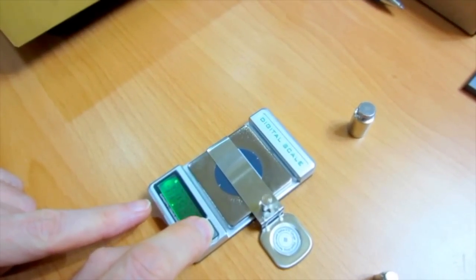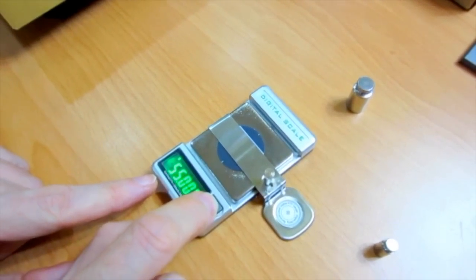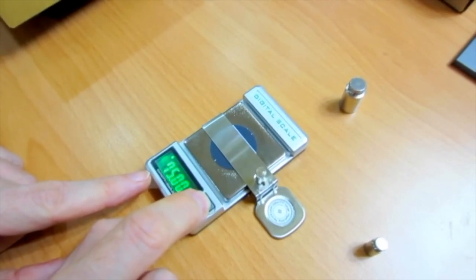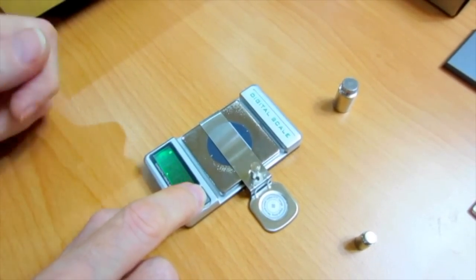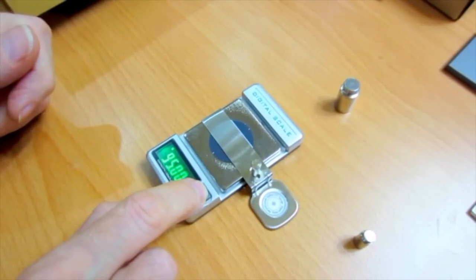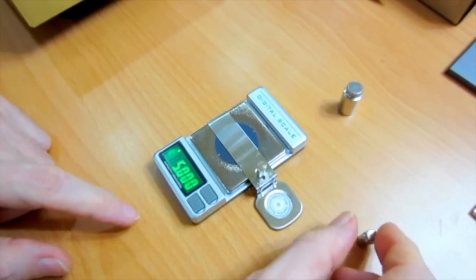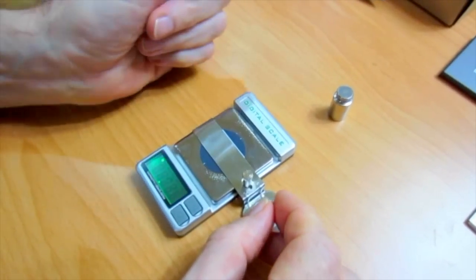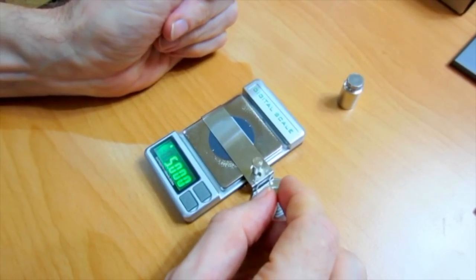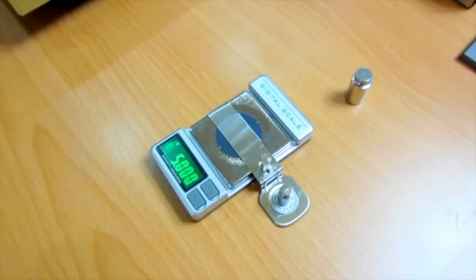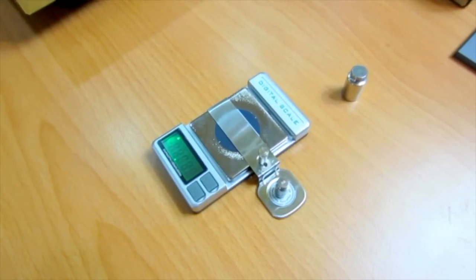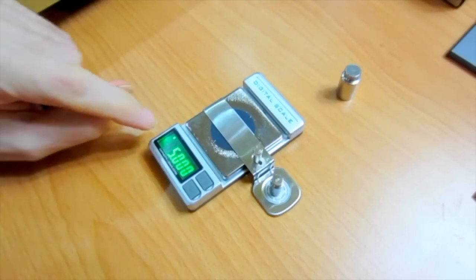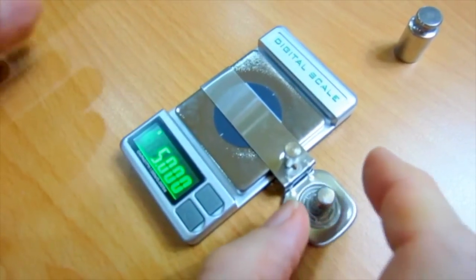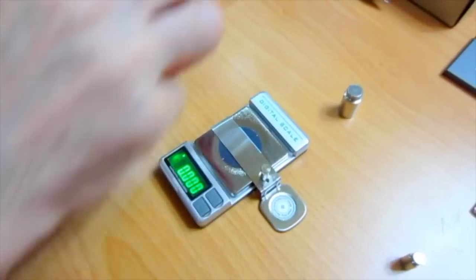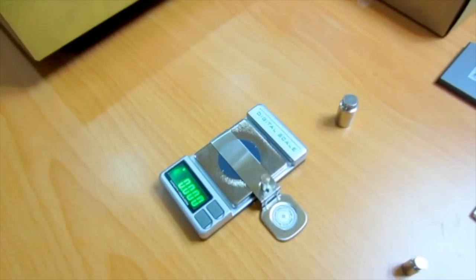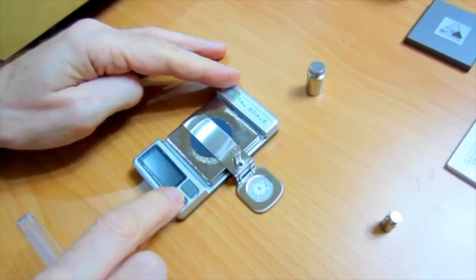A nice feature of this scale is you can calibrate for different ranges in 5 gram increments. So I could calibrate, for example, with an 80 gram mass. 85, 90, 95, 100, and 5. All right, while the 5 is blinking, it blinks for maybe 15 seconds, so you have to be quick. Put this in the center circle, stand back so you're not breathing on it. And when the 5 comes back and the gram unit here is steady, it's calibrated, ready to go. All right? Now before we actually make the measurement on the turntable, let me point out a few more features. Let me power this down for now.